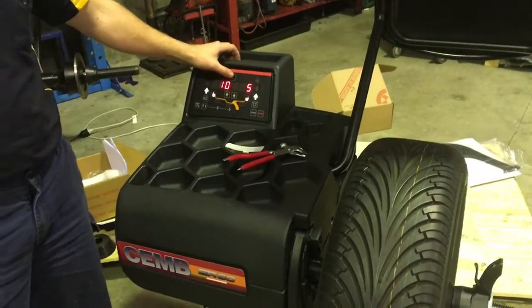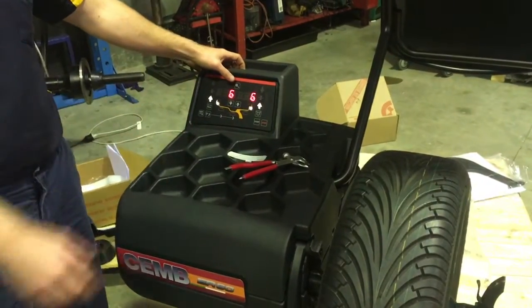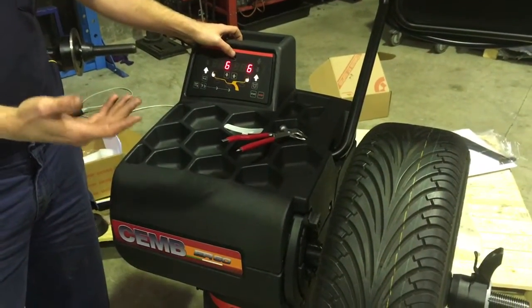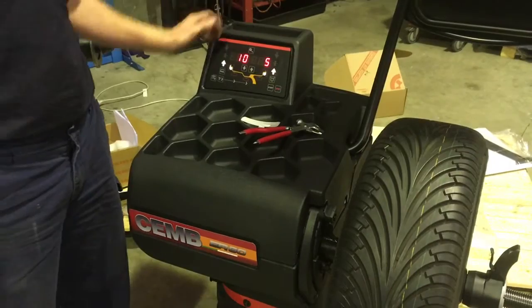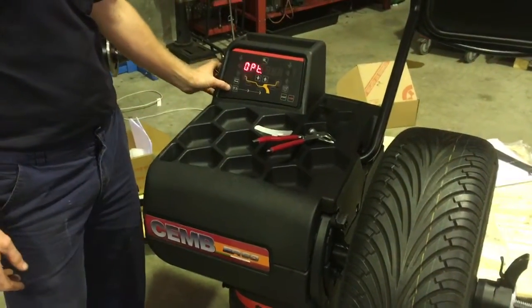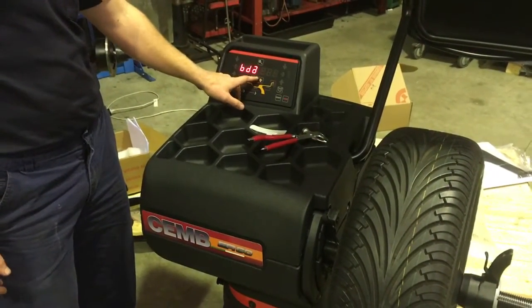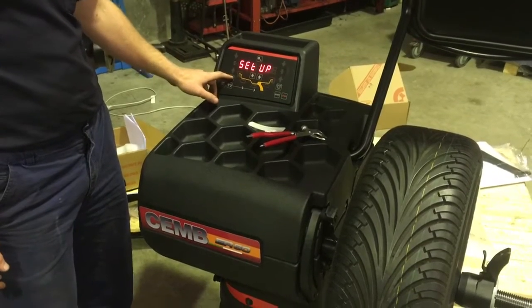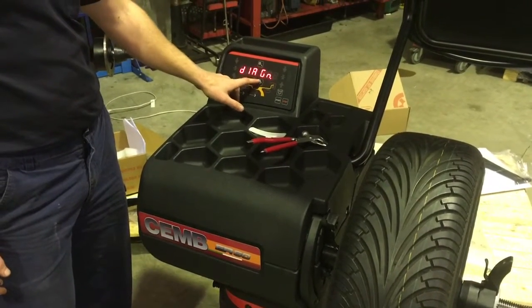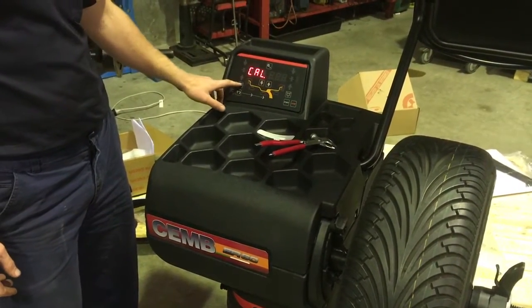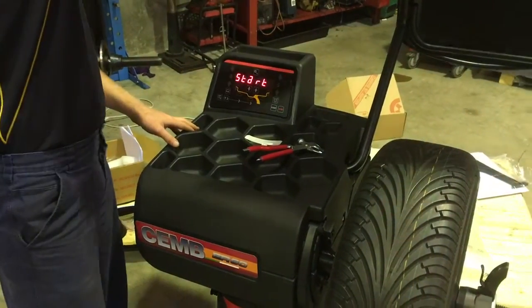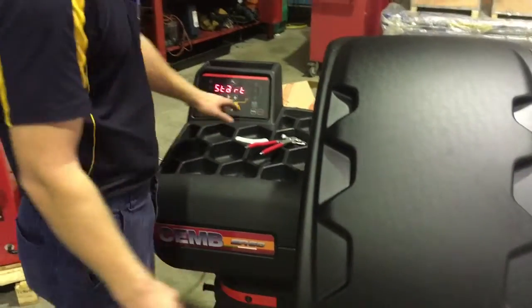So once we've got that, we're happy with that. We can do a test to see what the calibration is, or we can go and do the calibration. So first of all, we'll do the calibration, and then we'll test it afterwards to make sure that our calibration is right. So we press the menu key. Go down to setup. Go up to cal. Okay, now it says start. So we lower the hood, press the start button.